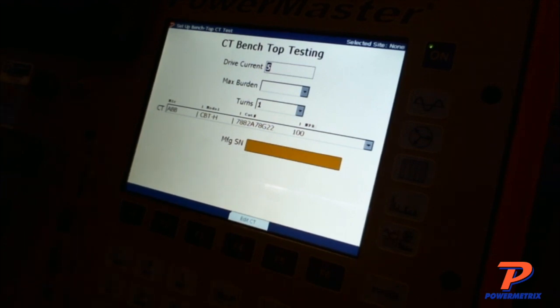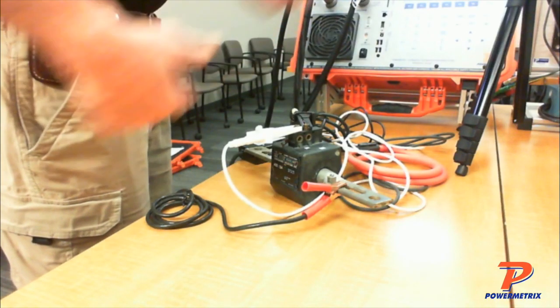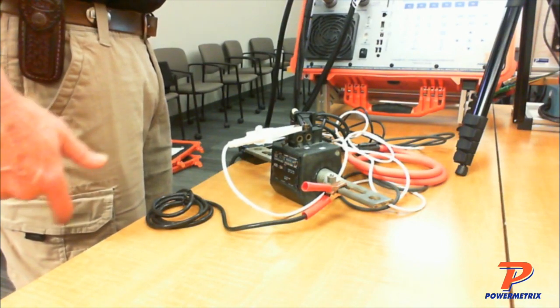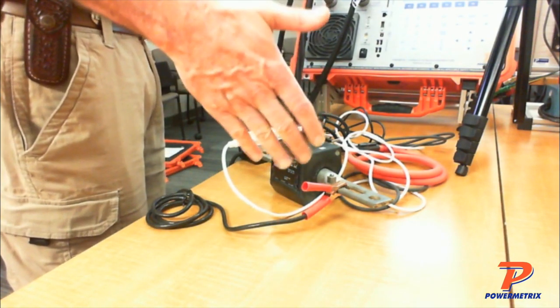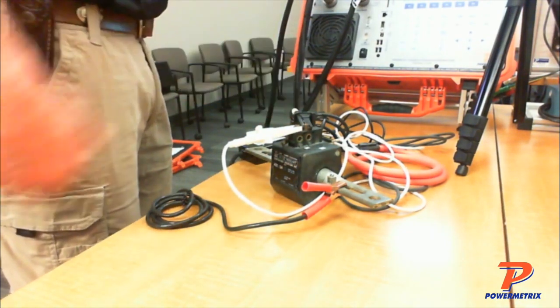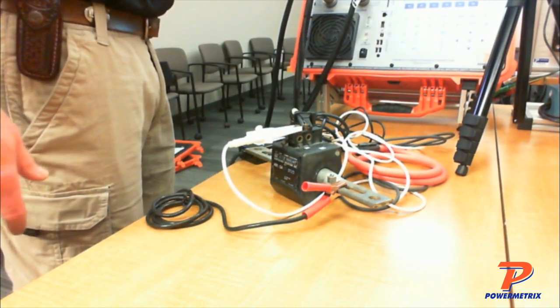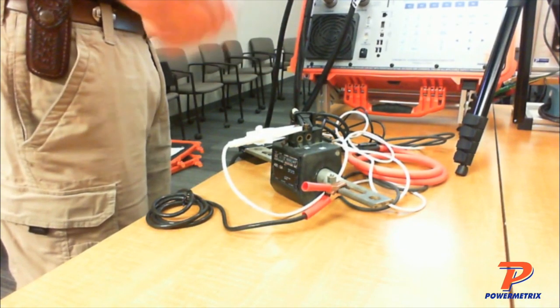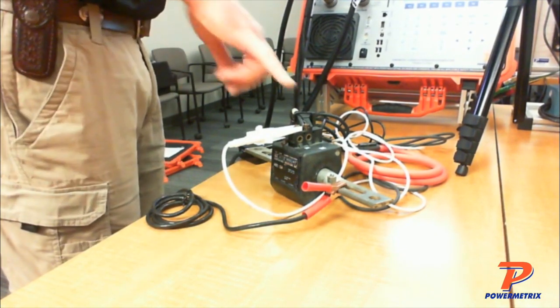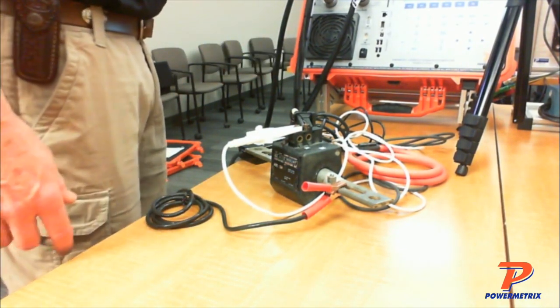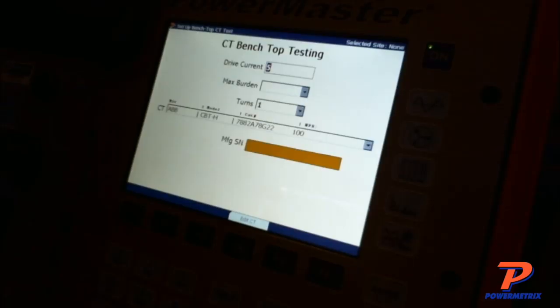Now we have to remember something with bar type CTs and using these, I can't do turns through there, right? So I'm limited to the size of the test kit. So the most I can ever generate on a bar type CT is going to be, for a 20 amp model, 20 amps. For the 50 amp model, it's going to be 50 amps because I can't put more turns through there and put more current through there. So in this case, I'm going to max it out. I have a 20 amp model and I'm going to put 20 amps through there.